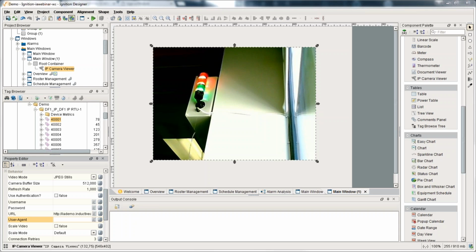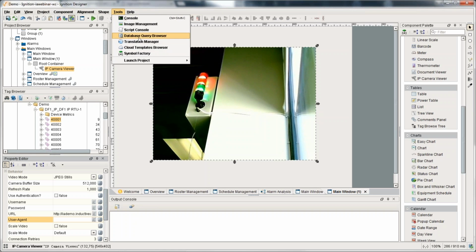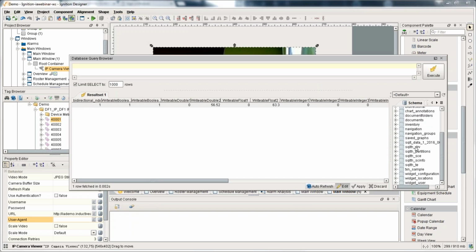We talk about integration. All right, Craig, can you query tag historian, or is that only for transaction groups? You can query the tag historian. The problem with querying it yourself is that we partition the data by default into multiple tables. So if you want to query 2 months, for example, you have to query 2 different tables. It's much harder for you to do that, whereas SQL Bridge just goes into one table, so it makes it much easier for you to query.